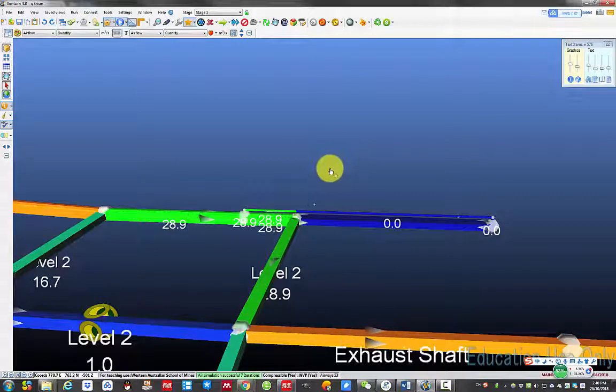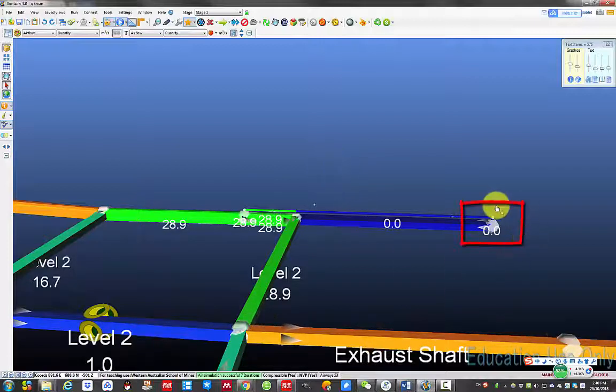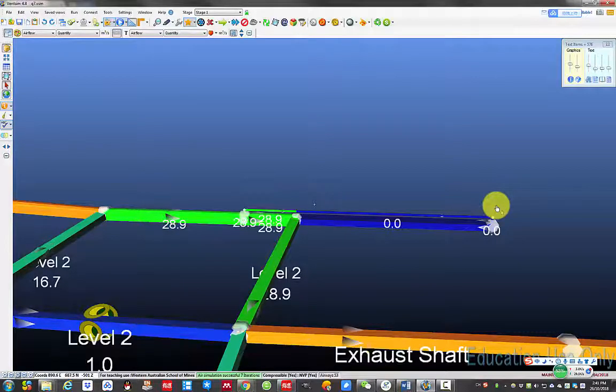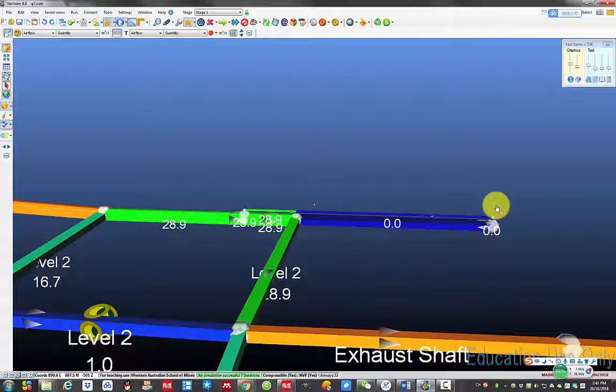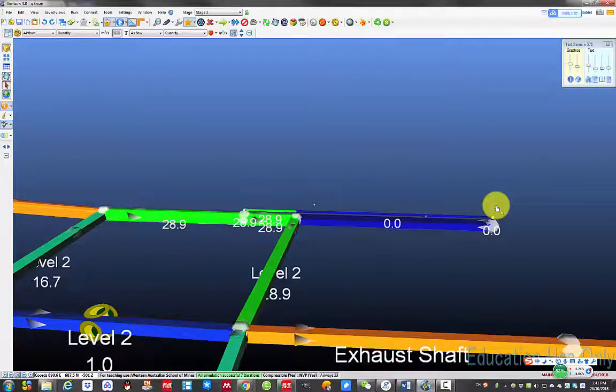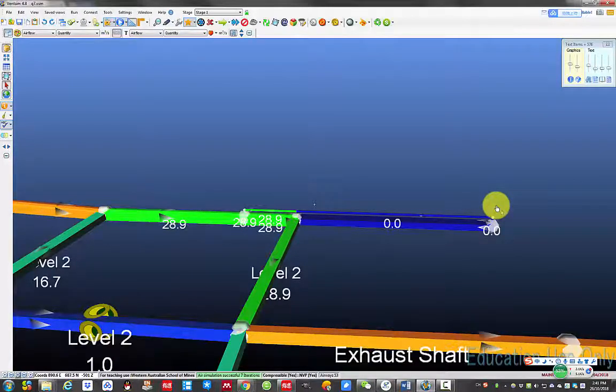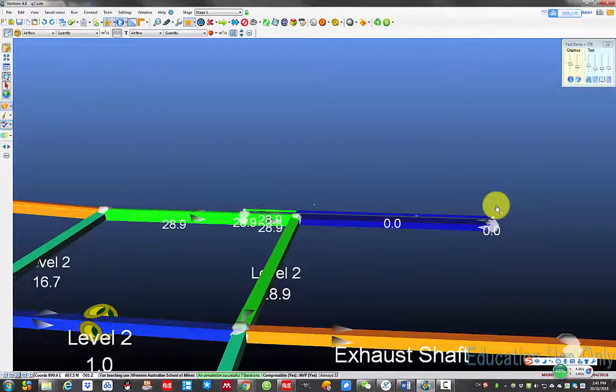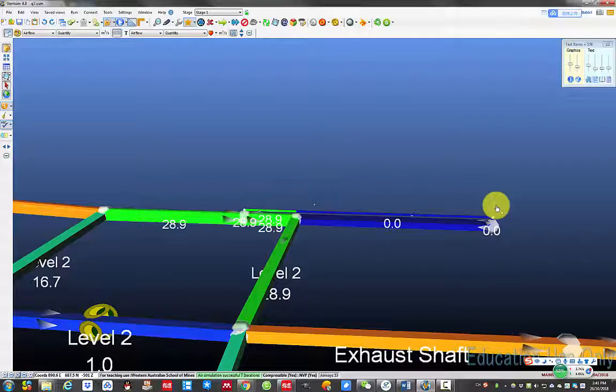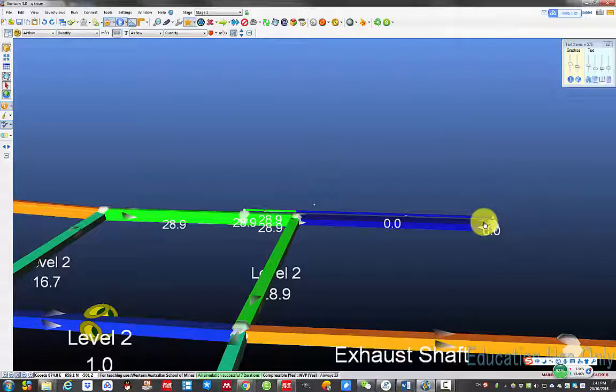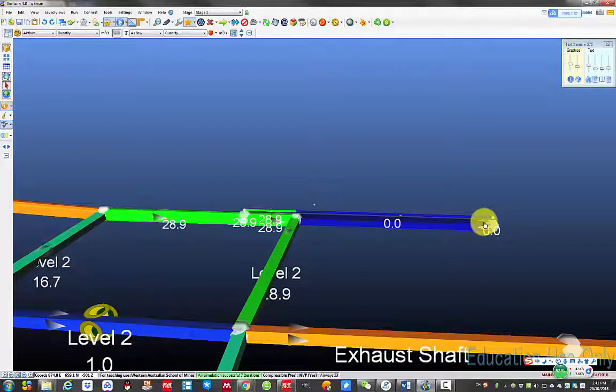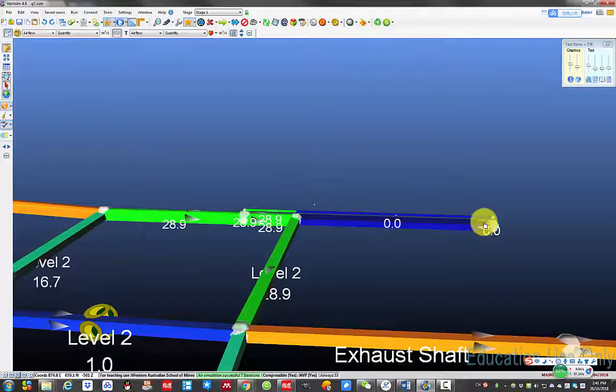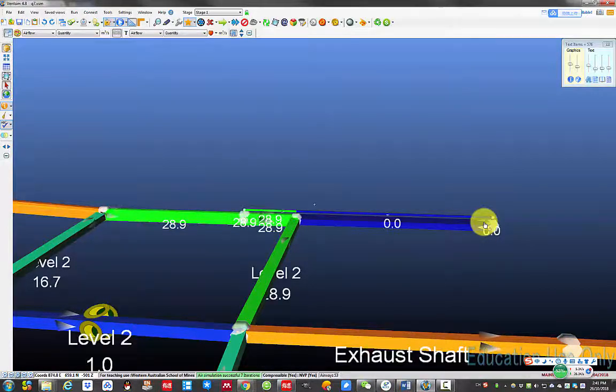The next thing we need to work out is how much air is needed at this heading. One major determining factor in a metal mine is the power of the diesel equipment. In Western Australia, the ventilation air requirements for diesel unit operations is 0.06 cubic meters per second per kilowatt of maximum rated engine output specified by the manufacturer. This means if there is a 300 kilowatt loader works in this development heading, the minimum required air flow to this heading should be 300 by 0.06 equals to 18 cubic meters per second.